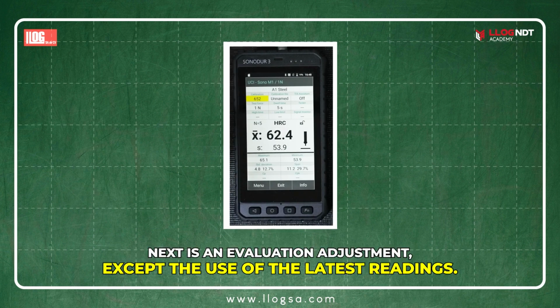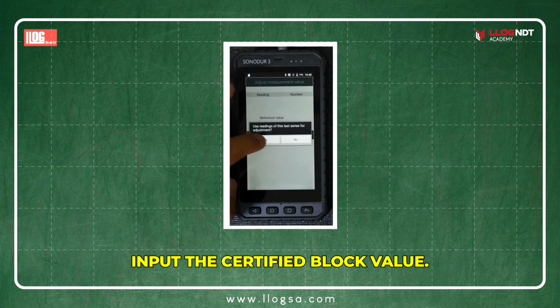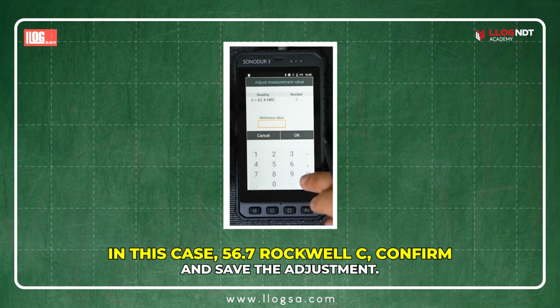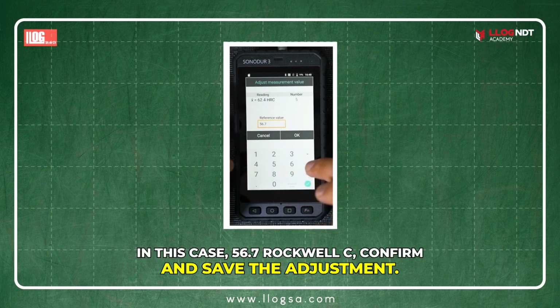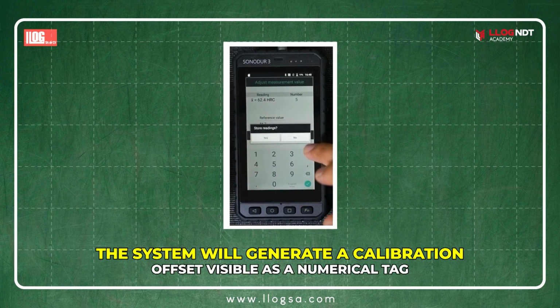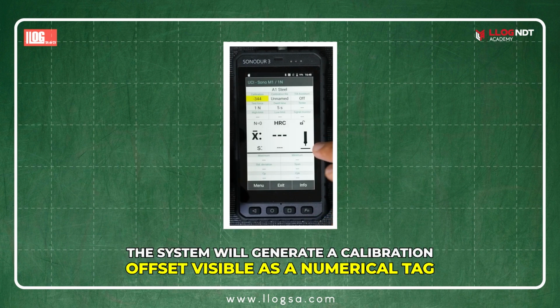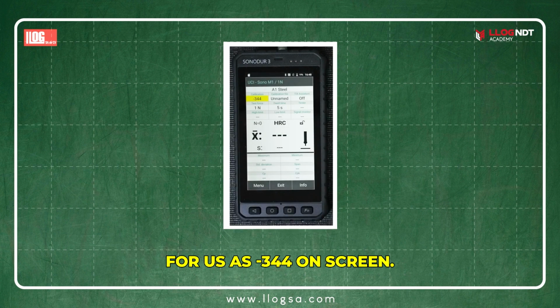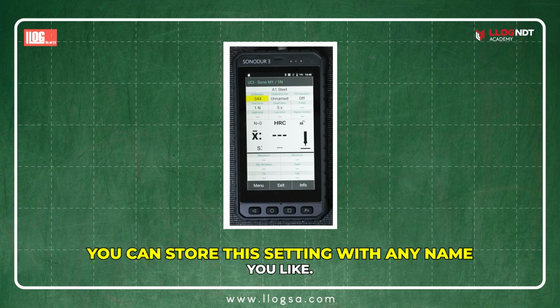Next, in evaluation adjustment, accept the use of the latest readings. Input the certified block value, in this case 56.7 Rockwell C. Confirm and save the adjustment. The system will generate a calibration offset, visible as a numerical tag, for us as negative 344 on screen. You can store this setting with any name you like.